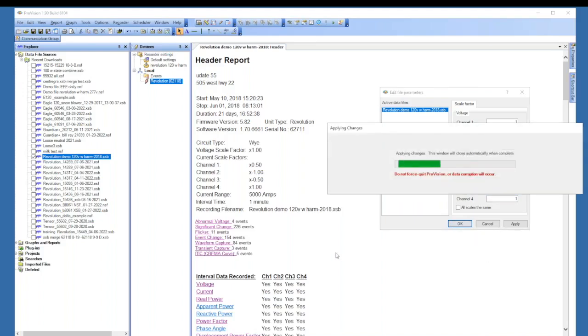Now, the other thing that you can do with scale factor is if you're recording on a secondary, you can put multipliers in there. And so if you have a 50 multiplier, you can put your 50 in there. I recently came in and someone had a current multiplier of 1,000 on their secondary. So you can put that in there, and then click OK again, and those multipliers would show up here, and then your voltage would be multiplied by whatever number you put in there, and your current would be multiplied by whatever number you put in there also.